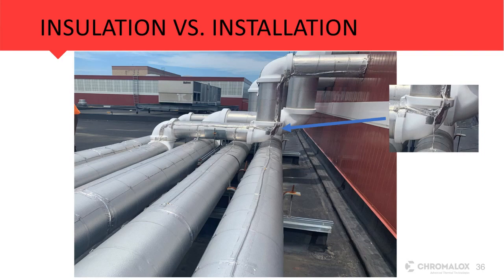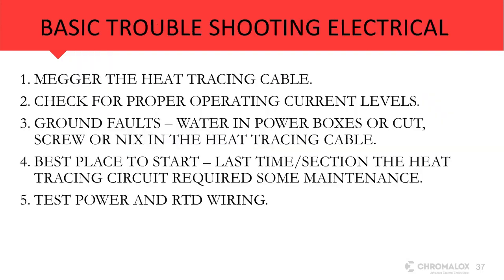Let's talk about electrical. So all of my electrical wires for power and RTD. One of the things we can do is go to the power box, megger the heat tracing cable, and make sure that it's meggering properly. We can check for proper operating current levels. A lot of times what you'll find if you have a ground fault, a couple of things could be happening here. We have water in the power box, or someone has a cut, or there's a screw or a nick in the heat tracing cable. A lot of times that comes from maintenance work that's been done.